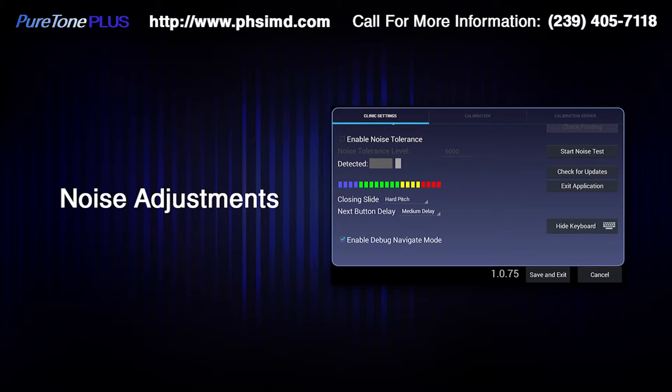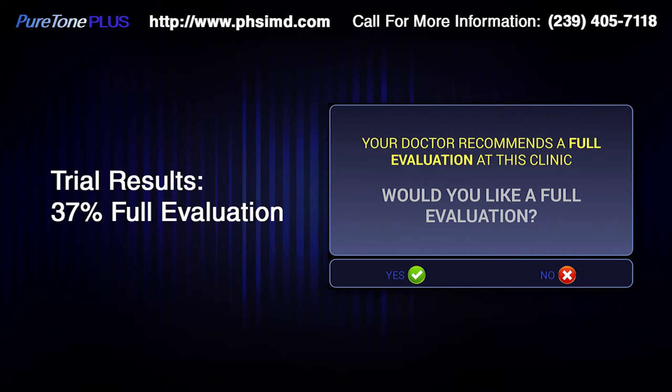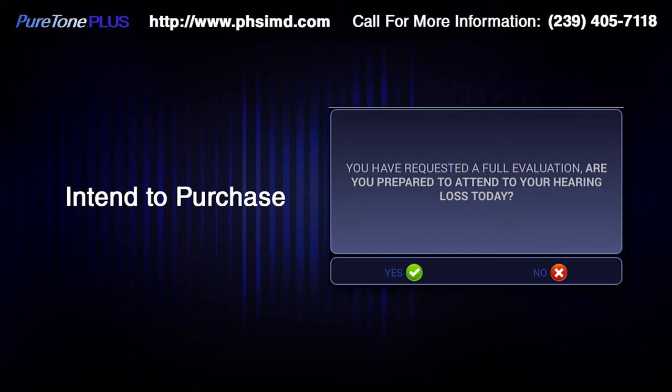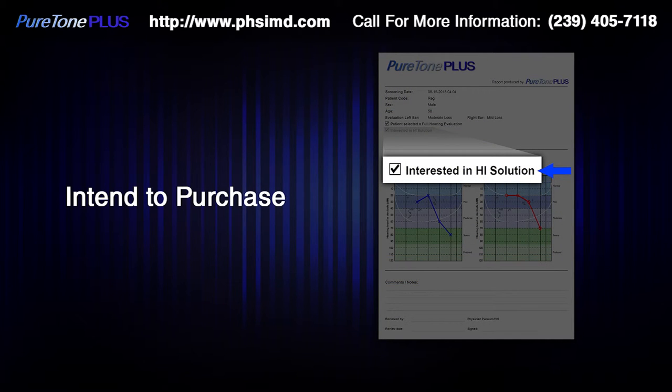While the screening test should be conducted in a reasonably quiet room, there is also a noise setting in the settings menu which allows the instrument to sense and repeat tones for a sudden unusual noise, such as a door slamming. After extensive trials, we have found that about 37% of patients over 60 years of age voluntarily selected a full hearing evaluation by a licensed hearing professional. To improve the number of patients who will actually purchase hearing aids, we also have an option in the settings menu of one of three questions to help identify patients who may be prepared to purchase hearing aids. The fourth option is to use no question at all — your choice to find the best option for you.